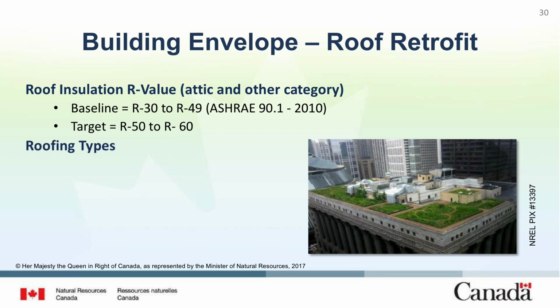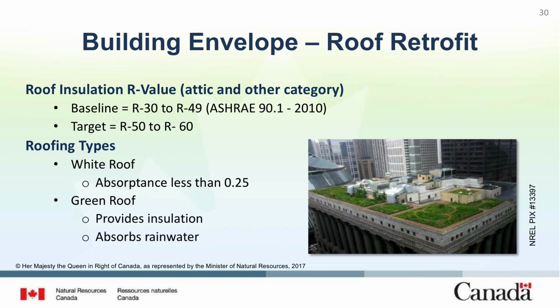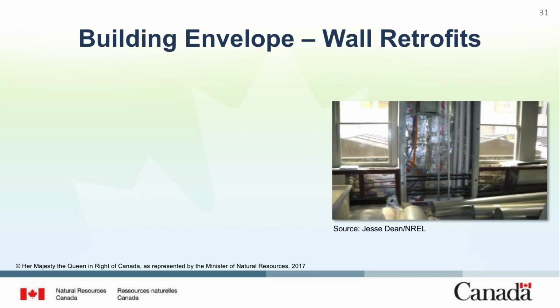Here's where an energy modeling program can help make sure you're aiming for an appropriate R value target. The R value should be determined through an iterative build and modeling process. Some other options to consider would be a cool roof, like a low absorptance white roof or a green roof. Green roofs have several benefits relating to reducing heat island effect and reducing runoff. Wall retrofits are some of the trickiest measures to implement. They are one of the more expensive retrofits in commercial buildings.